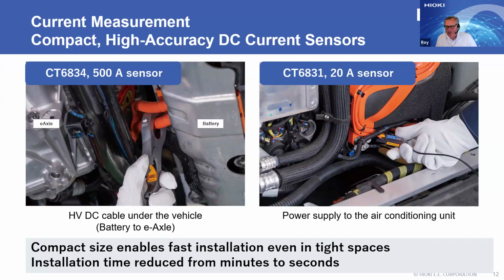It's mentioned that the dedicated current sensor probes are quite expensive. But to measure current accurately, these current sensors need high accuracy. Normal current sensors with BNC connectors typically have an accuracy of around 1 or 2%, whereas the HIOKI current sensors have a much higher accuracy. The latest current sensors we use for WLTP testing even have a base accuracy of 0.07%, which is necessary to fulfill WLTP requirements. That's why it's not possible to connect a regular current clamp with a BNC connector.